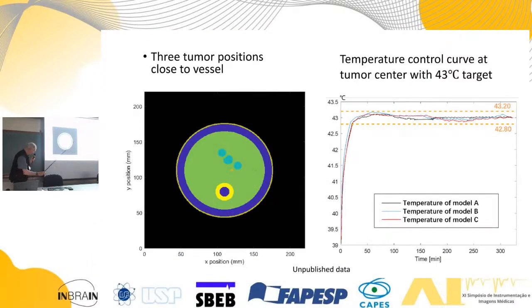And this was showing that you could raise the temperature up with this ring array using reasonable acoustic outputs up to the desired temperature and keep it within plus or minus a half degree, a quarter degree over time. It did take some time to actually get it heated up using that array with those limitations. So having an array that's got bigger elements and focused, it's easy to get a factor of 10 gain just by making the array bigger in the elevational direction and making it bigger in diameter and further out and higher so that you can focus and get a focal gain.